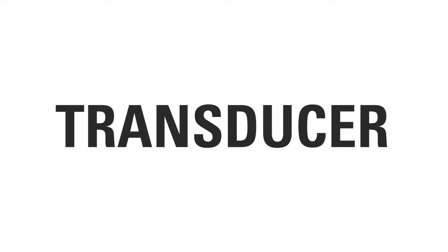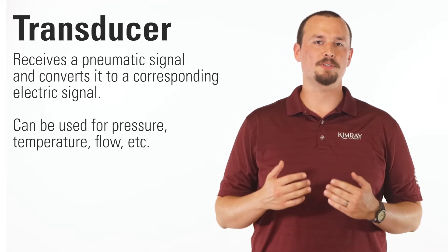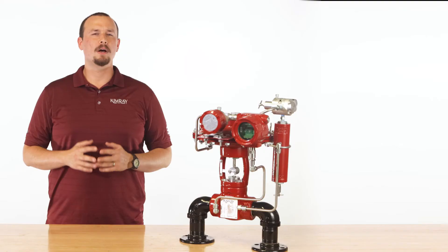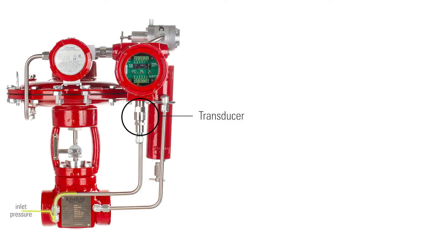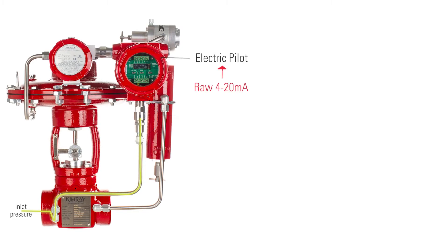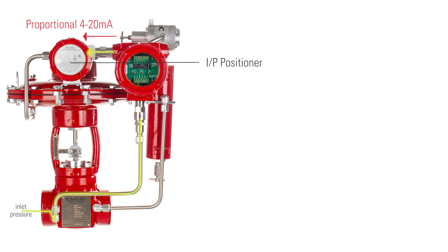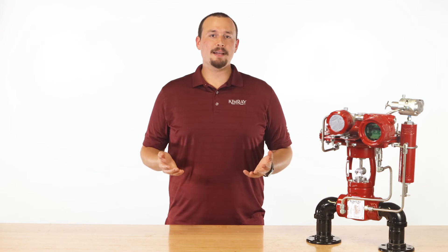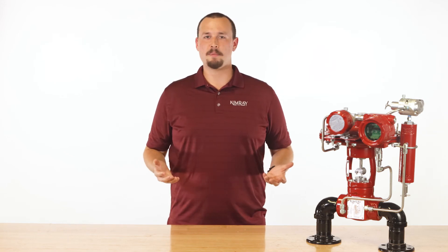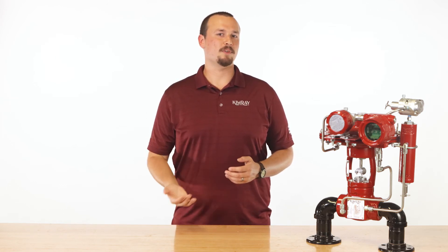Next, let's talk about transducers. The transducer receives a pneumatic signal and converts it to a corresponding electrical signal. One example of an I2P and transducer working together is on our electric valve controller. On this package, the transducer measures process pressure and gives a raw 4 to 20 milliamp signal to the pilot. The electric pilot then takes that signal and converts it to a proportional 4 to 20 milliamp signal and sends that to the I2P positioner. The I2P positioner converts that electric input signal to a corresponding 6 to 30 psi output signal and sends that level of supply gas to the high pressure control valve. Some people wonder why they need the pilot in this instance. Without the pilot, there is no decision maker. The pilot takes that raw transducer signal and converts it to an accurate, corresponding pressure.